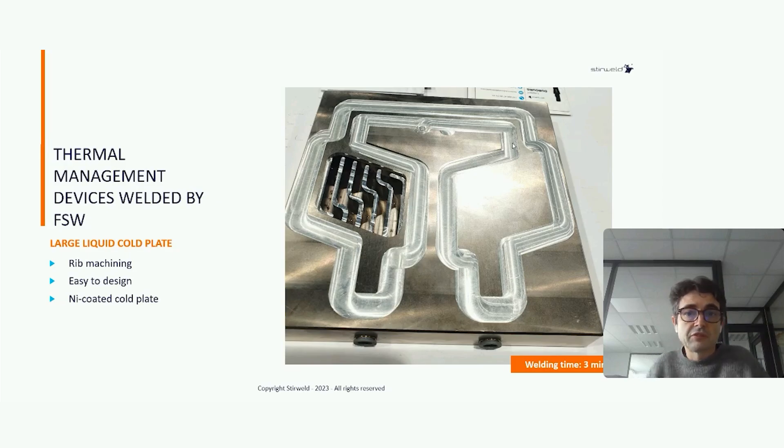Thanks to friction stir welding, we can weld an aluminum cold plate with nickel coating. This is possible because friction stir welding is a solid-state welding process. Otherwise, it is totally forbidden with classic liquid-state welding technology. The nickel coating is valuable for this kind of application because the water is very dirty, so by adding the nickel coating we achieve very high corrosion resistance.